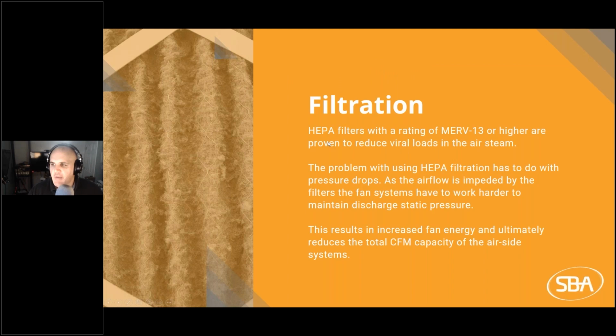Filtration. Now, you've heard about HEPA filters. Just so we're clear, HEPA is the filter, MERV is the rating of the filtration. I see a lot of folks who will say MERV filters and HEPA filters, and it's not MERV filters, it's MERV whatever is the rating. So essentially, as you go higher on the MERV rating, your ability to filter particulate matter increases. However, it also increases the restriction of air, and this causes pressure drops, sometimes very, very large pressure drops. So as airflow is impeded by the filters, these fan systems are going to have to work even harder to maintain discharge static pressure.